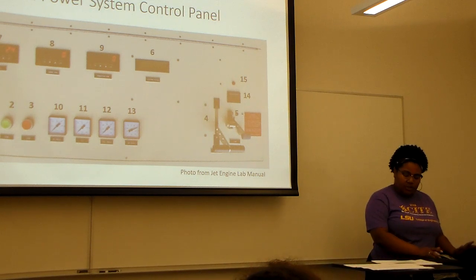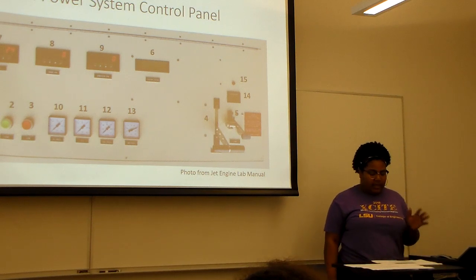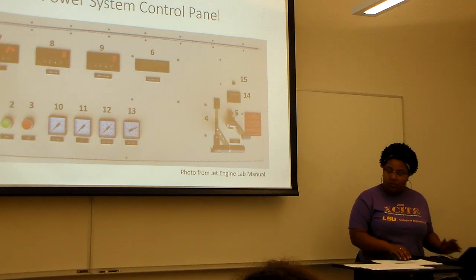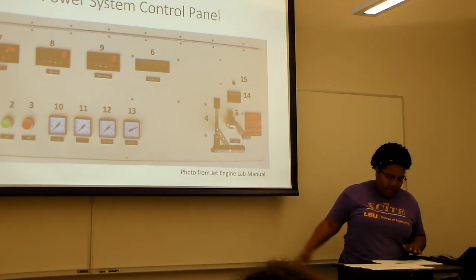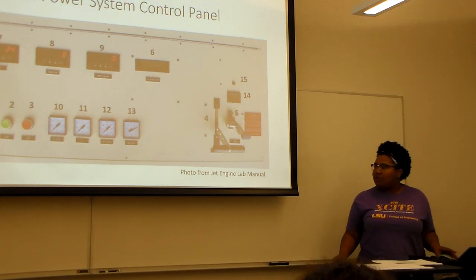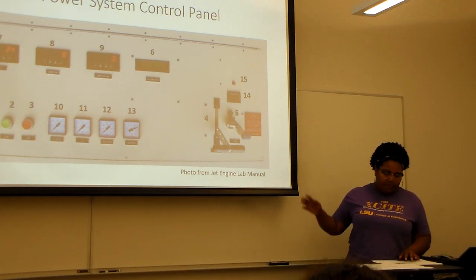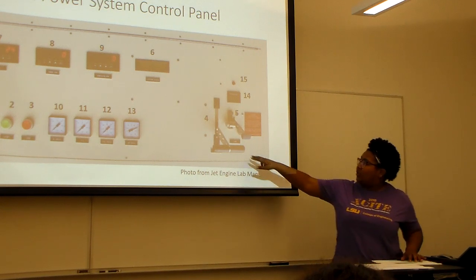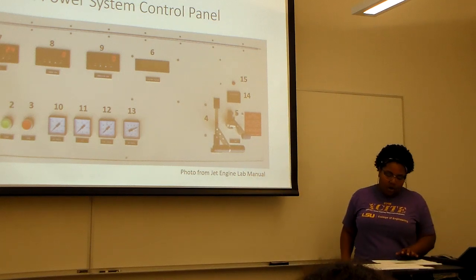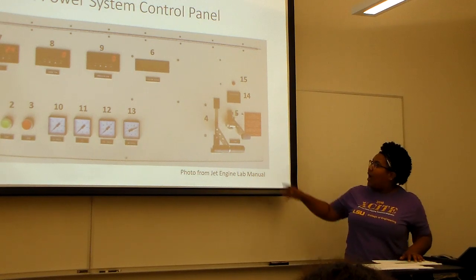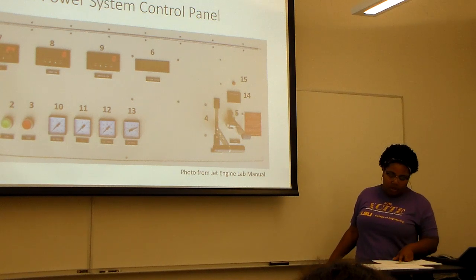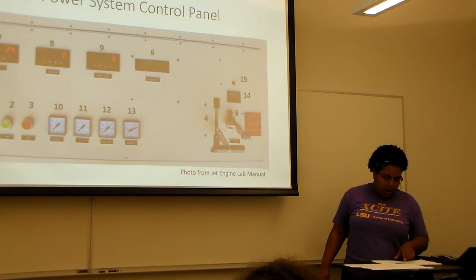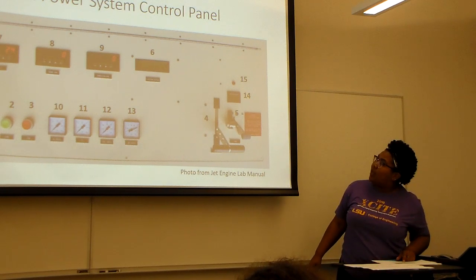So one is the master switch, which controls access and engine operation, which is here. And then the green start button, obviously, is green. That is the automated engine start and has some other functions. The red stop button means immediate engine stop. The T-handle power lever, which is 4, which is this one, is the engine RPM thrust control. And then 5 is the load lever, which is the blue handle, controls excitation loading on the electric alternator. 6 is the auto start LCD screen display.